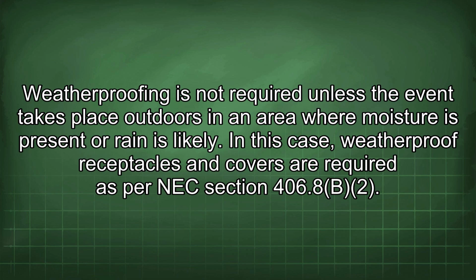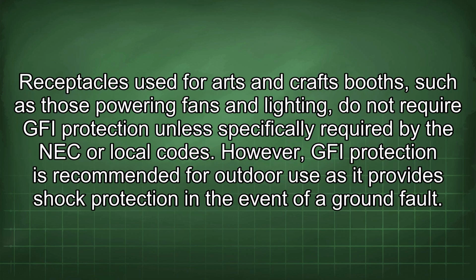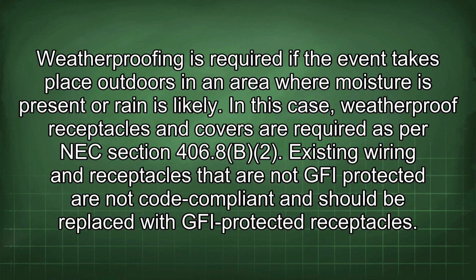In this case, weatherproof receptacles and covers are required as per NEC section 406.8(B)(2). Receptacles used for arts and crafts booths, such as those powering fans and lighting, do not require GFI protection unless specifically required by the NEC or local codes. However, GFI protection is recommended for outdoor use as it provides shock protection in the event of a ground fault. Weatherproofing is required if the event takes place outdoors in an area where moisture is present or rain is likely.